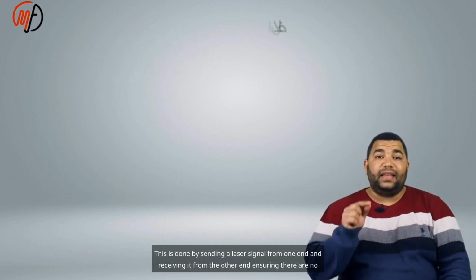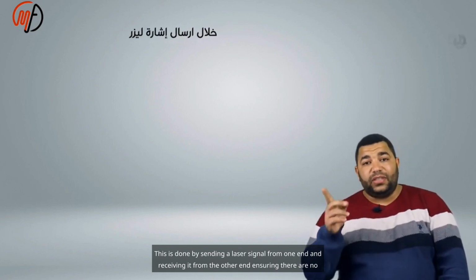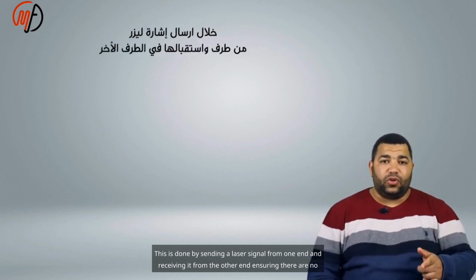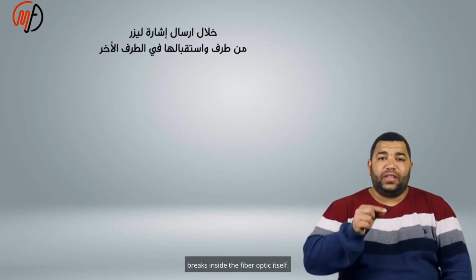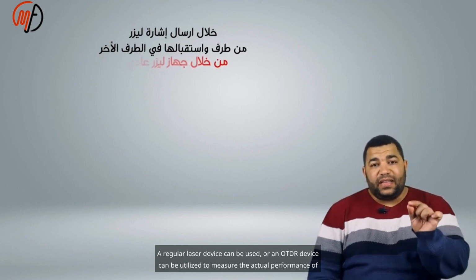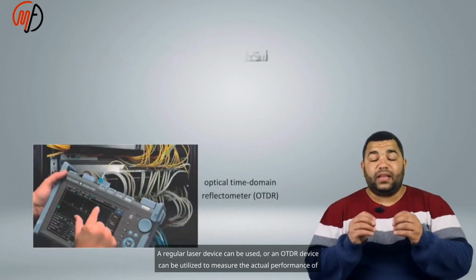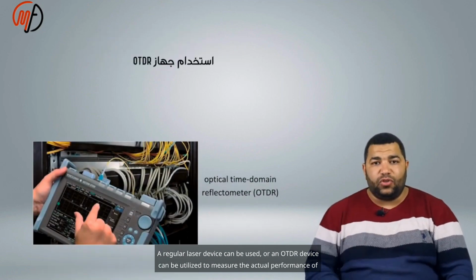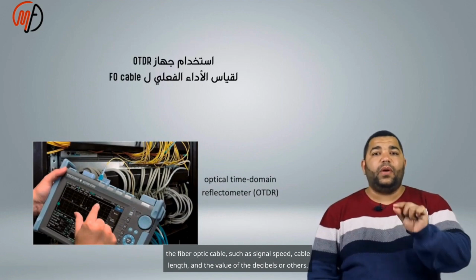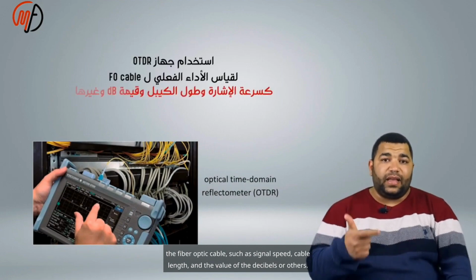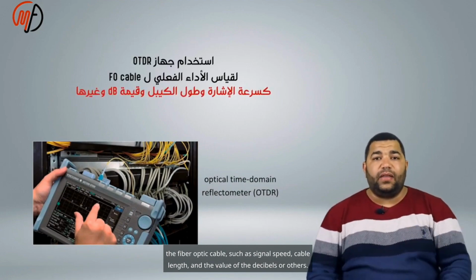This is done by sending a laser signal from one end and receiving it from the other end, ensuring there are no breaks inside the fiber optic itself. A regular laser device can be used, or an OTDR device can be utilized to measure the actual performance of the fiber optic cable, such as signal speed, cable length, and the value of the decibels or others.